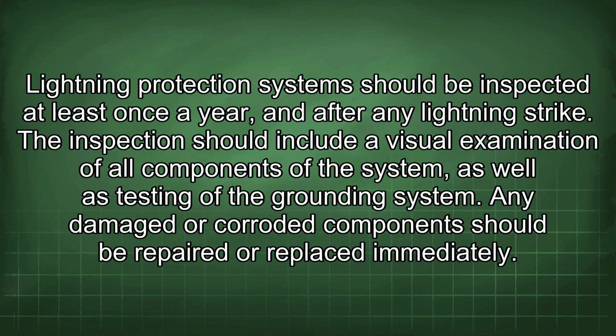Lightning protection systems should be inspected at least once a year and after any lightning strike. The inspection should include a visual examination of all components of the system, as well as testing of the grounding system. Any damaged or corroded components should be repaired or replaced immediately.